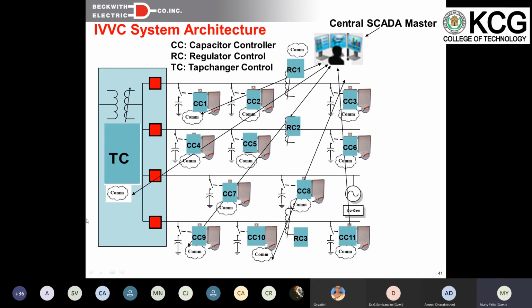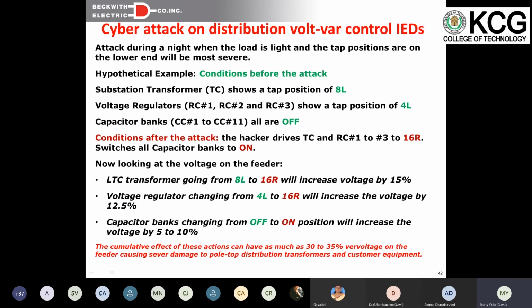You also have capacitor banks. If the power factor becomes bad, that means heavy lagging or heavy leading, the capacitor banks can be switched on and off to keep the power factor at unity and reduce the distribution losses. Distribution losses amount to several percent, and if you can help reduce them, you can save millions of dollars. That's what the IVVC system, or a Volt-VAR optimization system, does, but it uses heavy communications back and forth. If your communication system is attacked by a cyber attack, you can get into trouble.